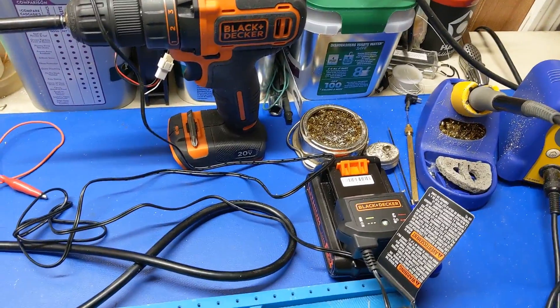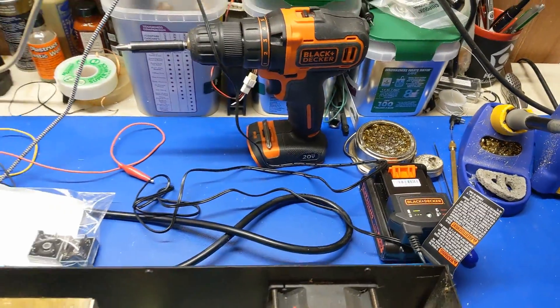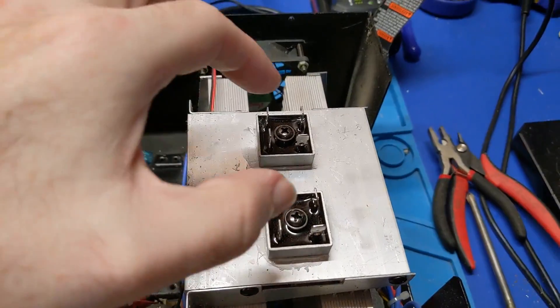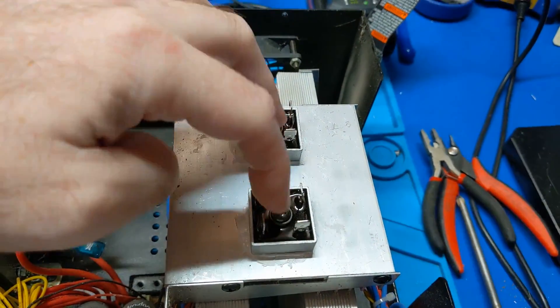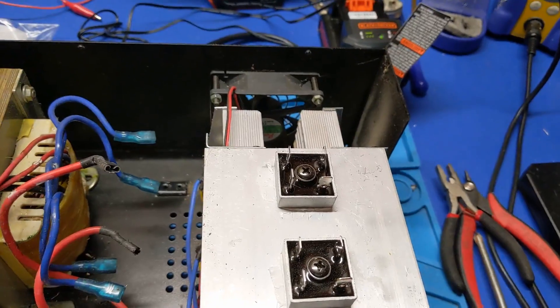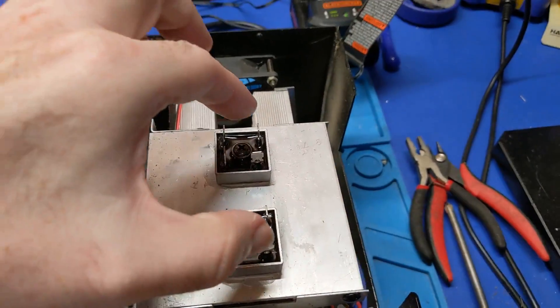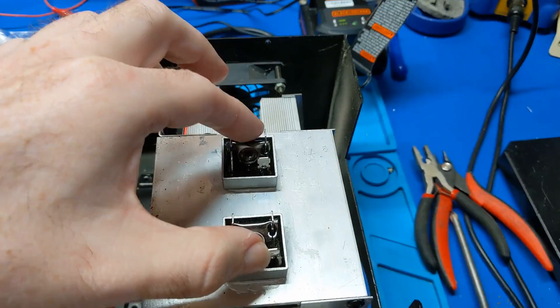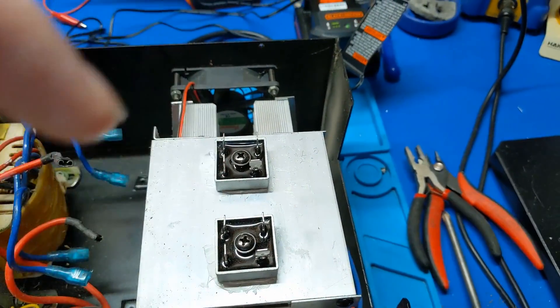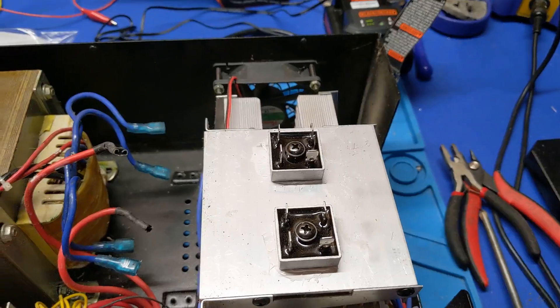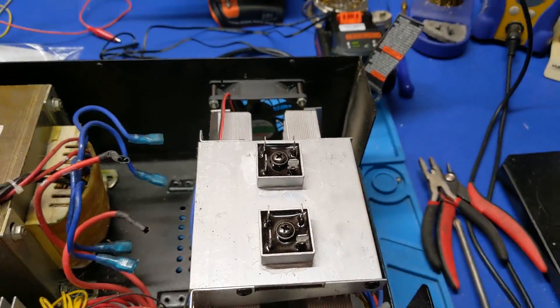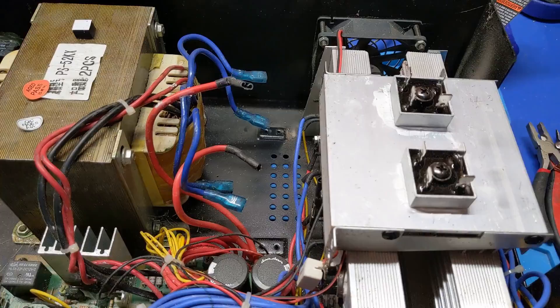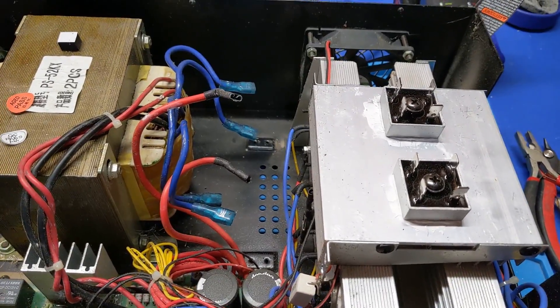Just in time, the battery died on my drill. But one thing I noticed right away is these two screws were very loose, they weren't tight at all. They were just, they weren't even finger tight. And I'm wondering if these backed out, if that's why the one rectifier failed, because it couldn't dissipate the heat properly. That's entirely possible. So I went ahead and changed both rectifiers. So we're just going to go ahead and get this thing put back together and we're going to test it.